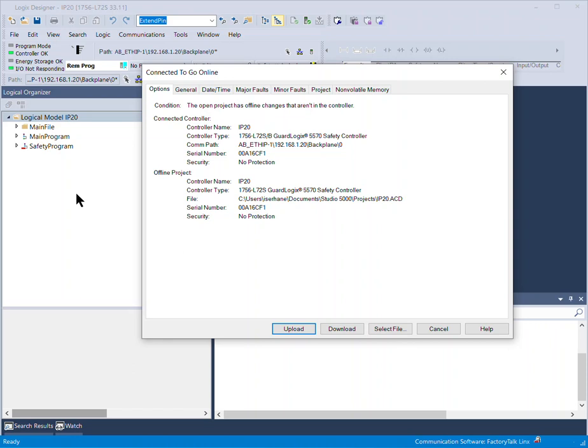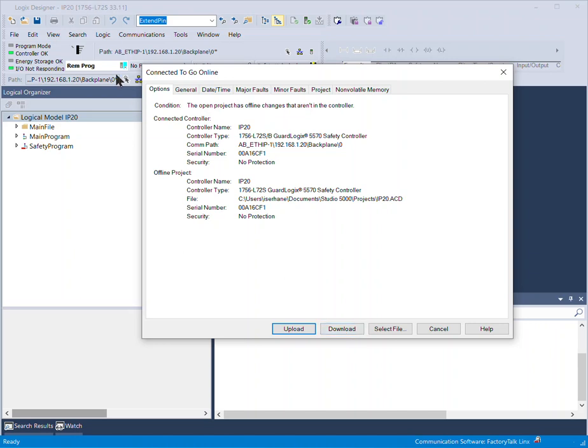But if I'm designing a new project or updating a project offline and I want to go online and I'm certain about it, I can download. But you have to be aware that when you download, the PLC will go to offline and the system will be in program mode, it's not going to be in run mode. So be careful when you do that because you don't want to stop any process or operation.